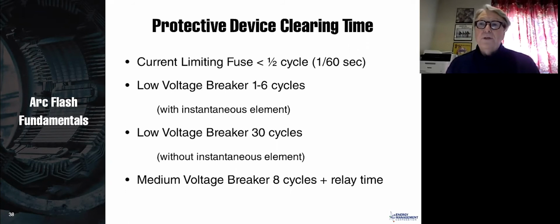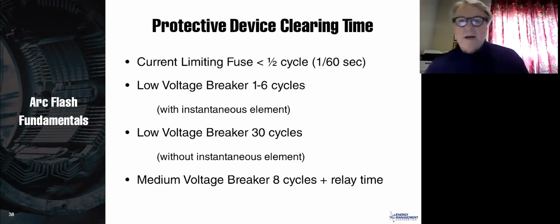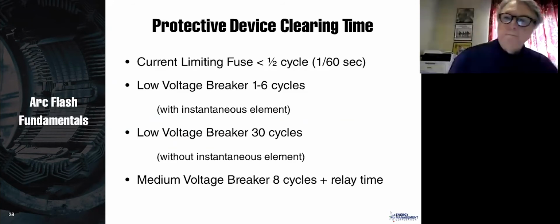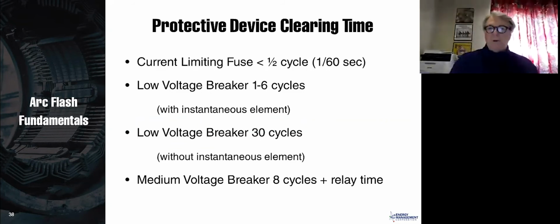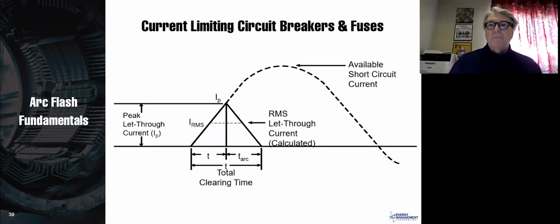Current limiting fuses typically interrupt in less than half a cycle. Low voltage breakers, 1 to 6 cycles. A low voltage insulated case type breaker without an instantaneous element could take up to 30 cycles. Medium voltage breakers could be up to 8 cycles. The old air breakers were 8 cycles. Newer breakers are 3 and 5 cycles. But that's just an indication of how fast things interrupt.